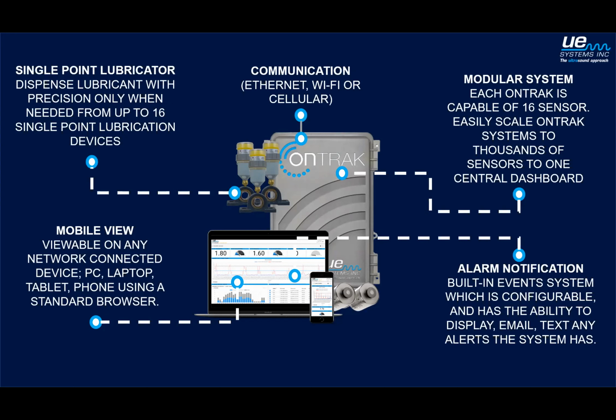16 sensors and 16 single point lubrication devices means you can have a bearing that is completely monitored and remotely precision lubricated, or you can have a combination. It doesn't mean every sensor has to have a single point lubricator. In fact, they can be added after the fact. You can start with the sensors and add lubricators later, or have 6 sensors with lubricators and the other 10 without.